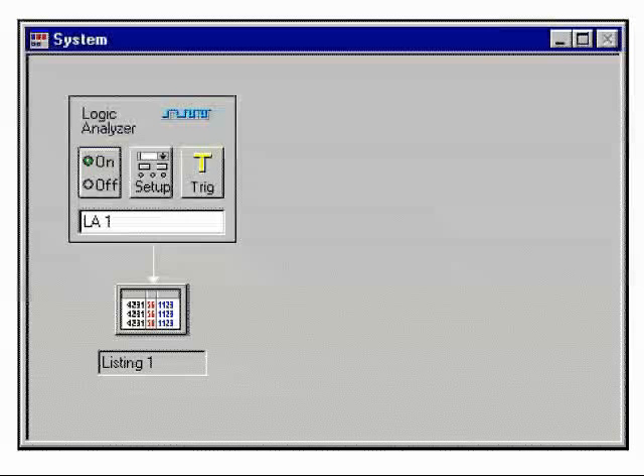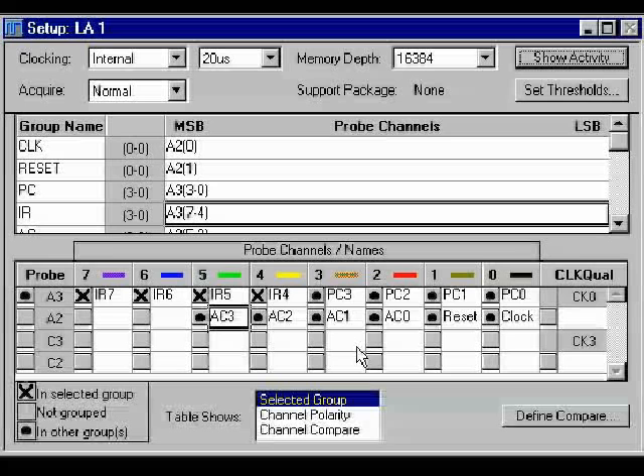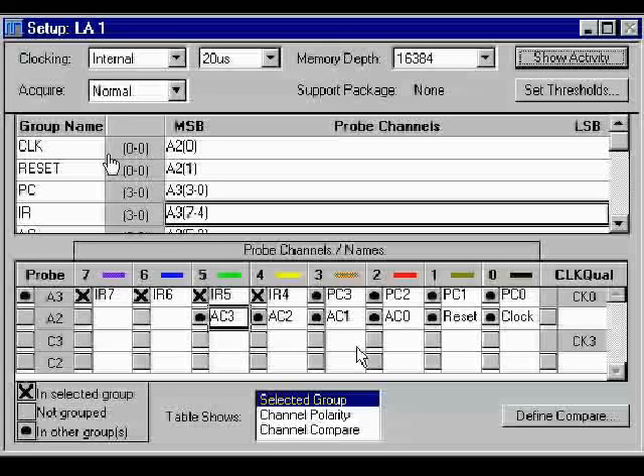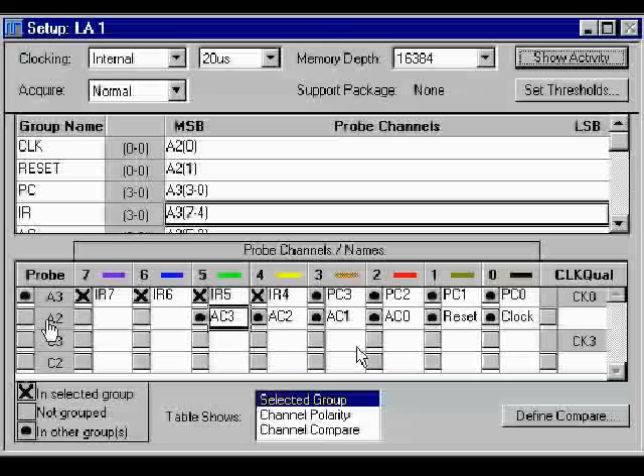Now let's go back to the system module. At this point, you're going to select Setup. Once you enter Setup, type in your Clock, Reset, PC, IR, and AC. These are the groups that you want to watch. Under Clock, you have only one signal. You'll tie that to the connector A20. Reset will be tied at the connector A21. You designate this group down here. A20 is Clock, so you have to type in Clock here. Reset's at A21.